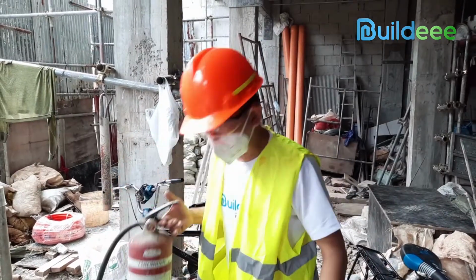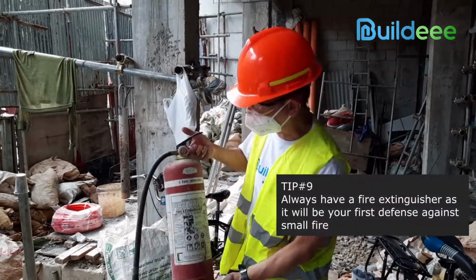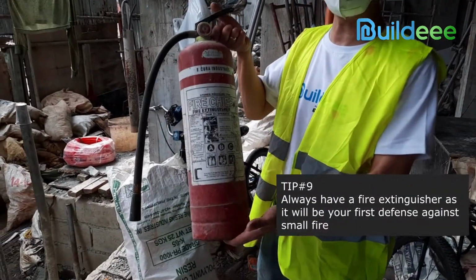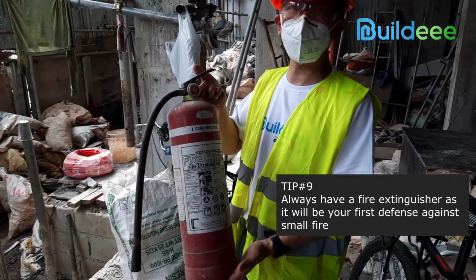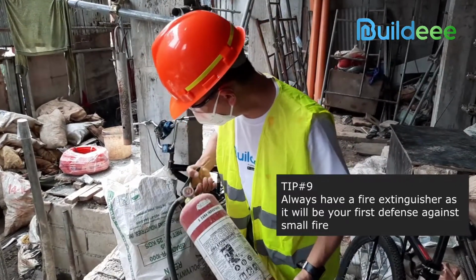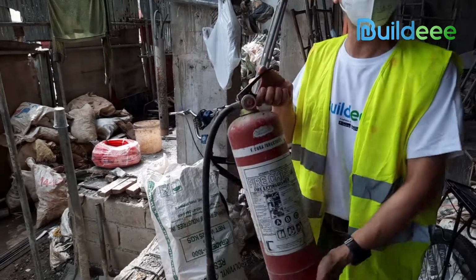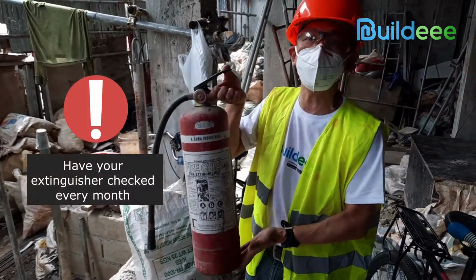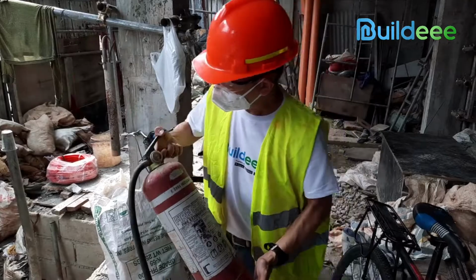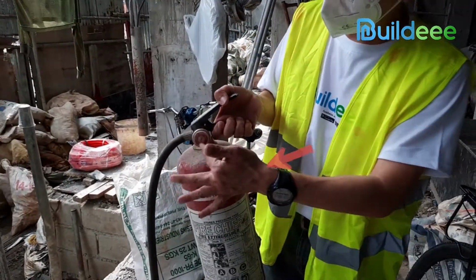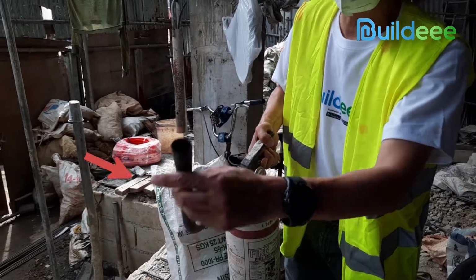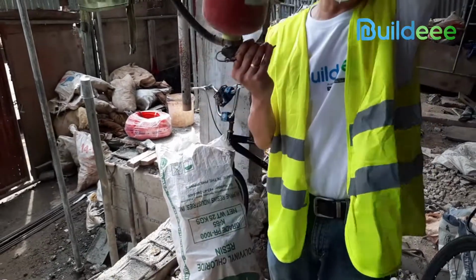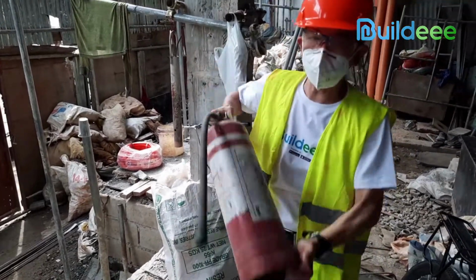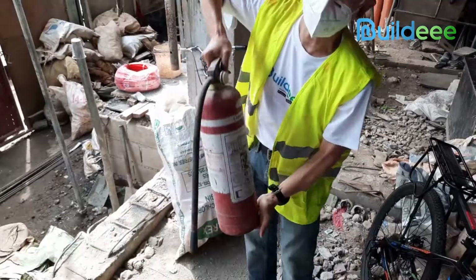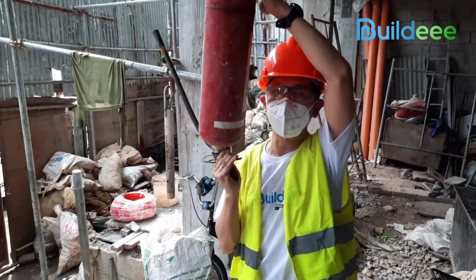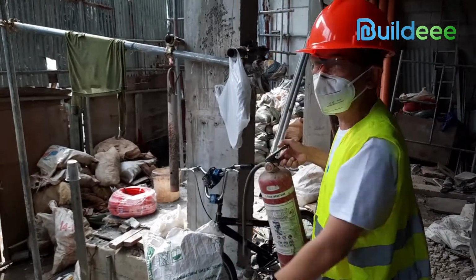Number 9. The fire extinguisher is what we call the first line of defense against small fires. Every construction site must have a fire extinguisher ready for use. Unfortunately, this fire extinguisher has lost pressure, so it is important to have your extinguisher checked every month. How do you check? Check the gauge to see if it is in the green. Check the hose for any blockage. Flip the extinguisher three times so that there is no caked powder inside. And make sure it is placed in an accessible area.